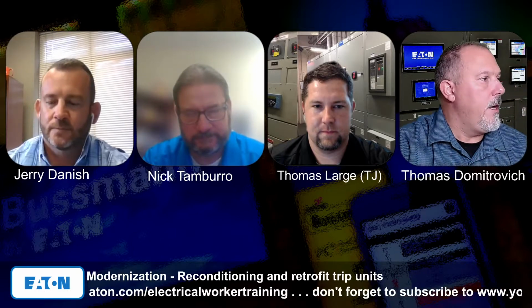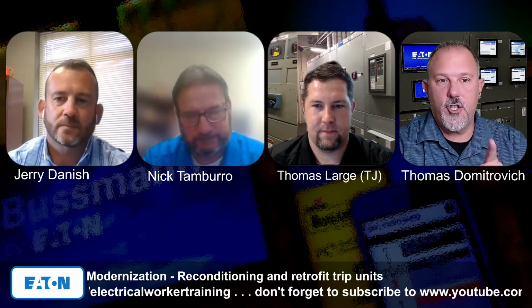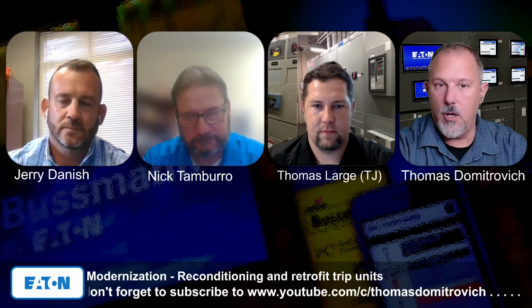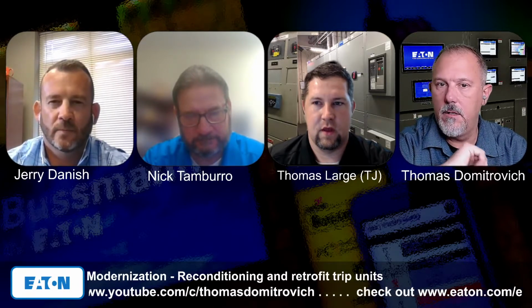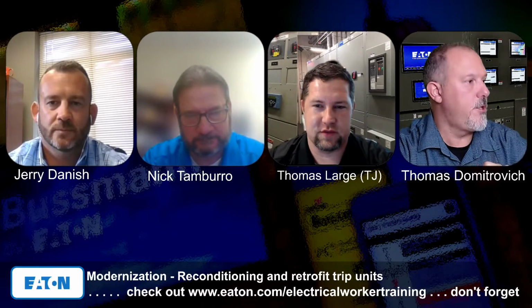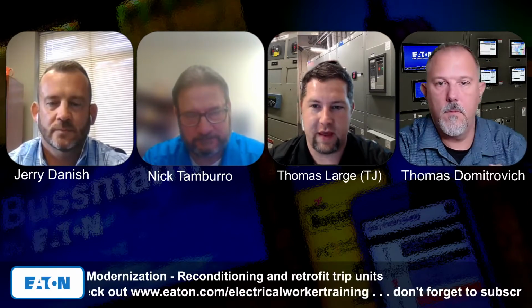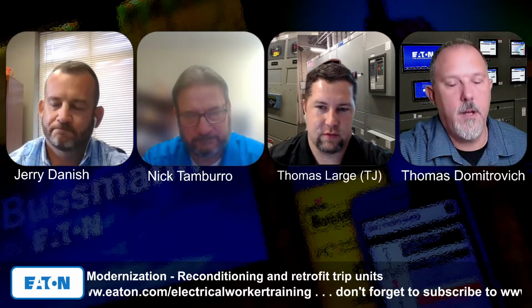Yeah, so electronic trip unit is not a relay, right? Those are two separate things. Electronic trip units would be something on a circuit breaker, whether medium voltage or low voltage. It wouldn't be a relay, right TJ? Correct. So when you talk about trip units, that's going to be specific to your low voltage breakers. Protective relays are more geared towards your medium voltage, which lives external of the actual breaker device.